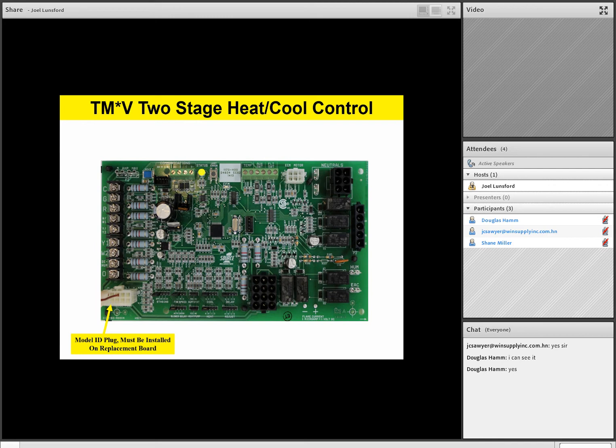And so it's important that if you have a replacement board, you take the model ID plug off the old board and you snap it onto the new board. As soon as you power up the new replacement board, it'll automatically know what size furnace it's hooked up to because of that model ID plug. So this is very, very important. We stress this if we sell a replacement two-stage variable speed board like what we're looking at. We want to make sure and remind the technician to take the model ID plug off the old board and snap it onto the new board, because that way the new board will know what size furnace it's hooked up to. So that model ID plug configures the board for the size of the furnace it's hooked up to.